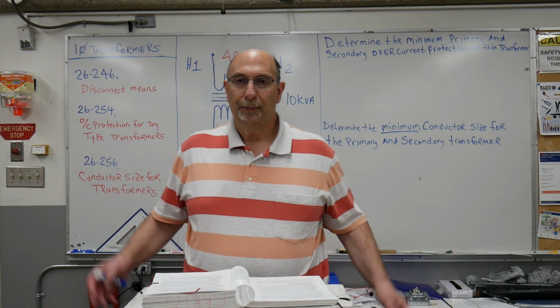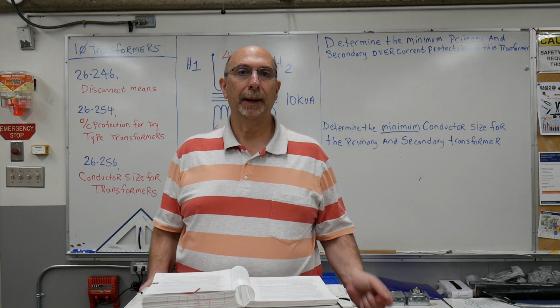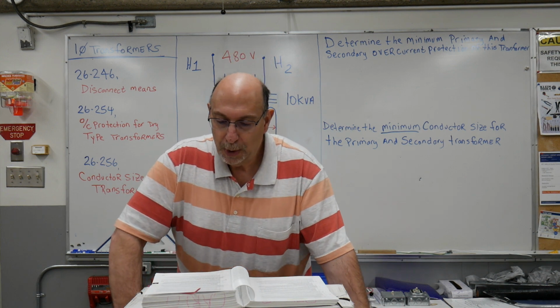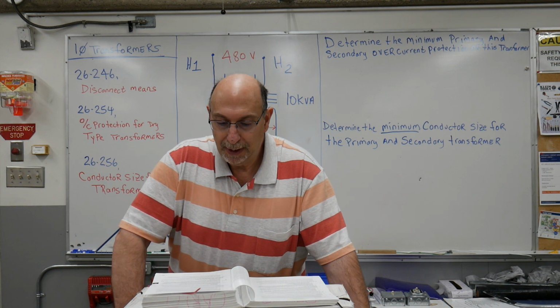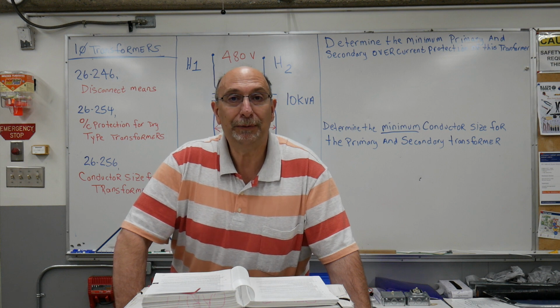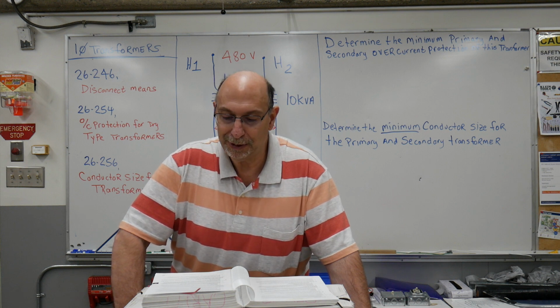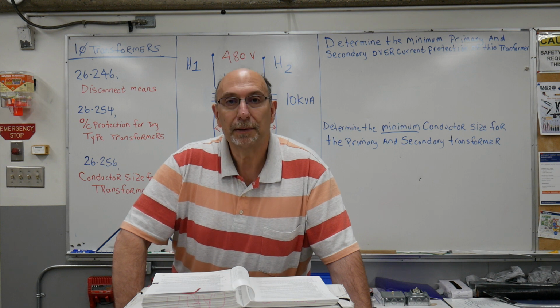So in reality, because of heat, which is our number one biggest problem with transformers, we have to keep a minimum, as per sub-rule 1, 150 millimeters away from any combustible surfaces. So that is 6 inches.